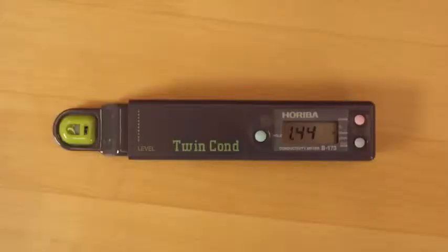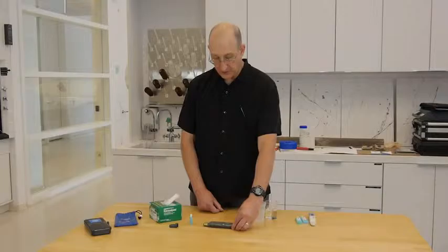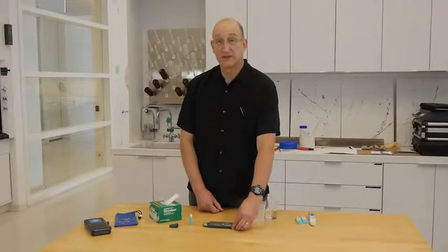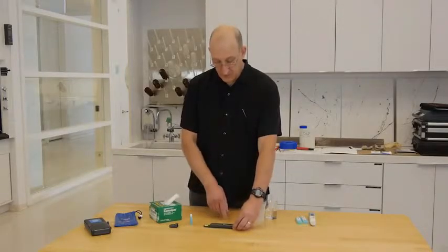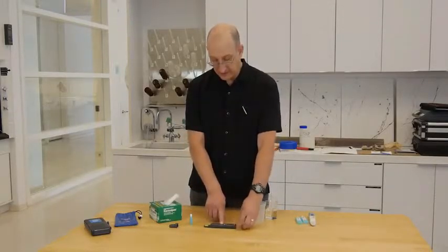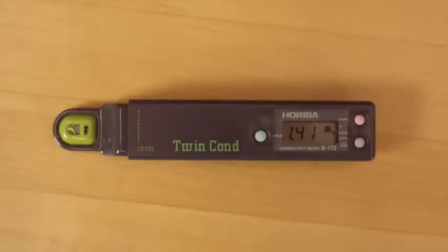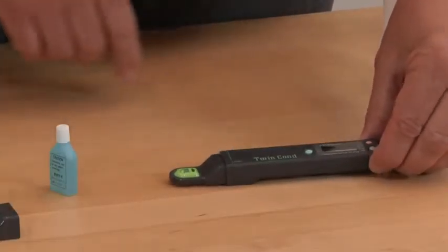solution, wait for the reading to stabilize, which is indicated with a small happy face, which we now have. And you can see right now we're reading at 1.44 millisiemens, or 1,440 microsiemens. We push the calibrate button, and we go into calibration mode. You can see the little symbol there for calibration mode. And it's calibrated to 1.41 millisiemens. And when we get a happy face, we're all done. So we have our happy face.